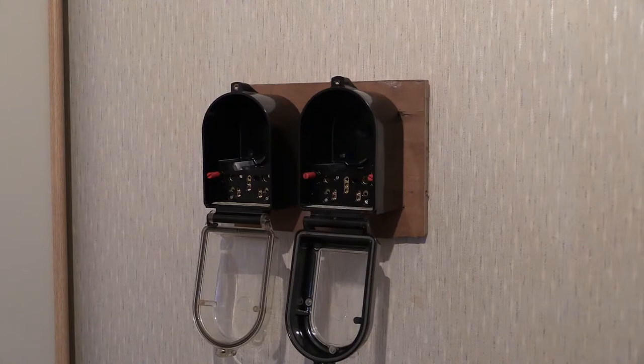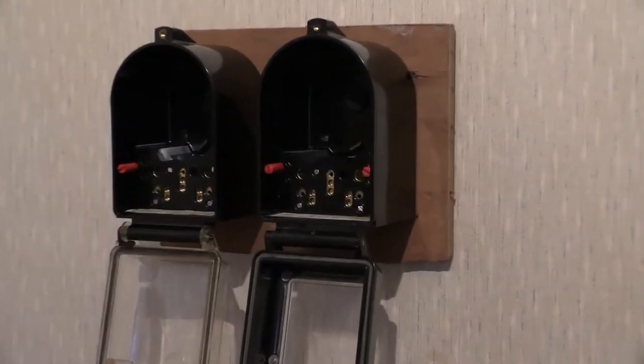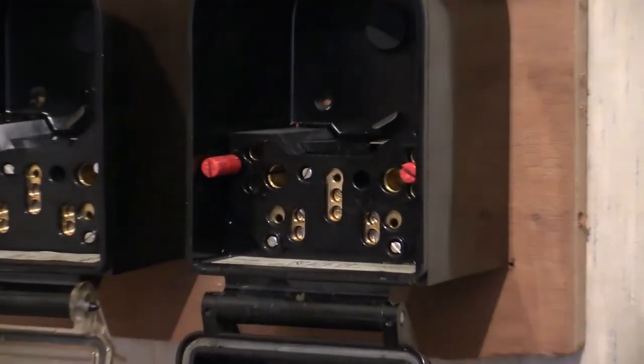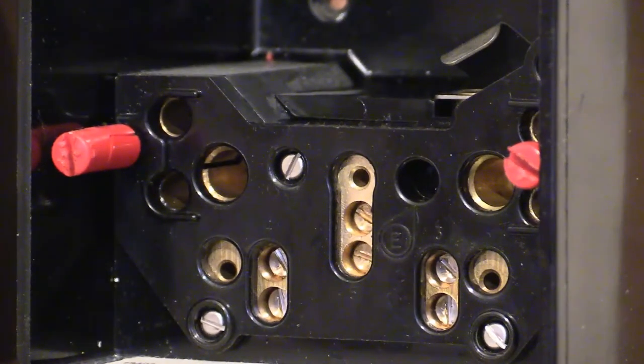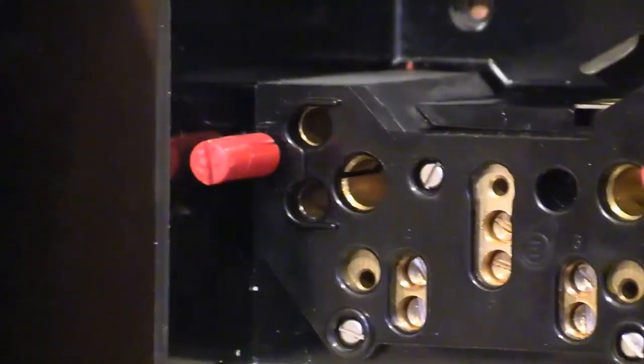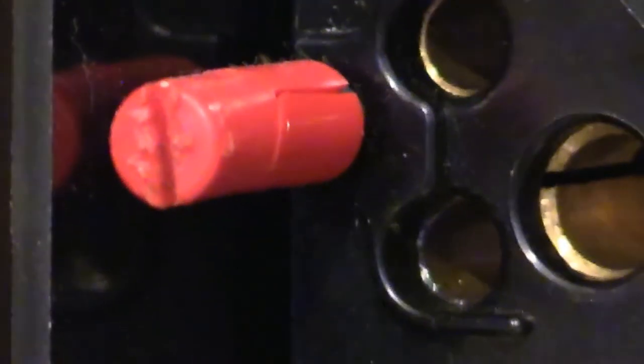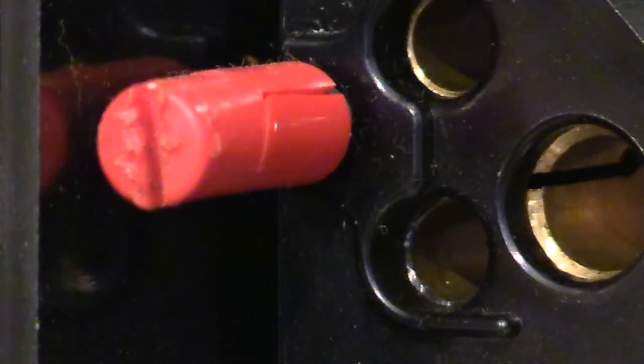We shall zoom in now and have a look at the terminals that are in there. We shall be observing the case that's on the right, but what I show applies to both of them. As you can see, we can now see the two plastic headed clamping screws. The one to the left, unfortunately, has got splits in it, so that could fail anytime soon. These time switches are from the early 1970s, so they're very well used. That's got splits and cracks in it. It is known that some of these do crumble to pieces, and then the time switch needs to be removed in a nice controlled fashion.